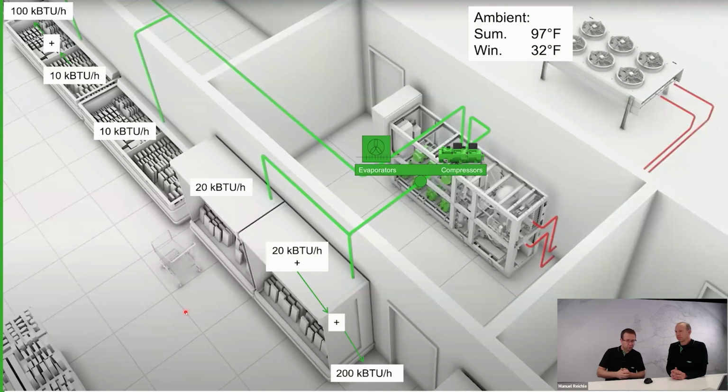It's also a question what you assume there. For my example now, I assume that I have to go with 40 kBTU out of that situation, which means that only two of the big ones are on. So in total, we have installed 360 kBTU in this combination here.